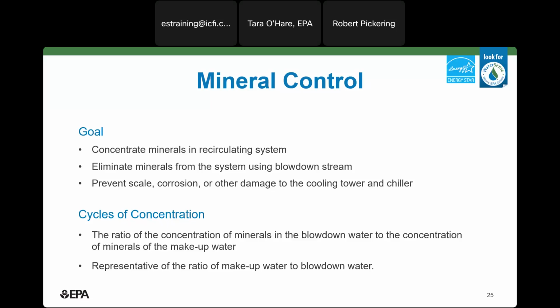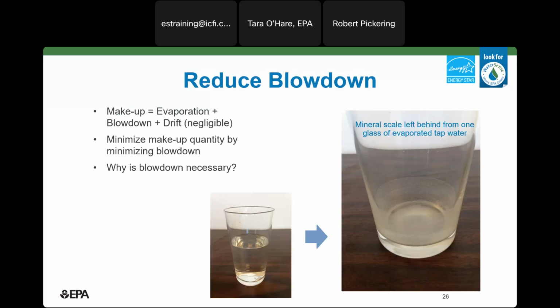A measure of this efficiency is called cycles of concentration, which is really the ratio of the concentration of minerals in the blowdown to the concentration of minerals in the makeup water. It's also representative of the ratio of makeup volume to blowdown volume. So the higher the cycles you get, the less blowdown is occurring.